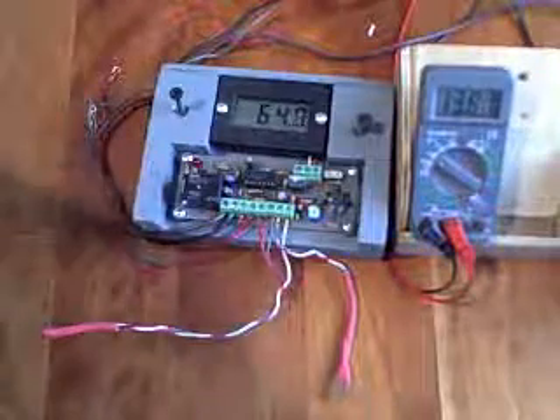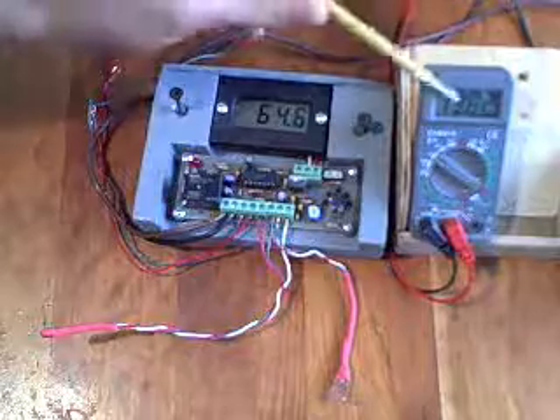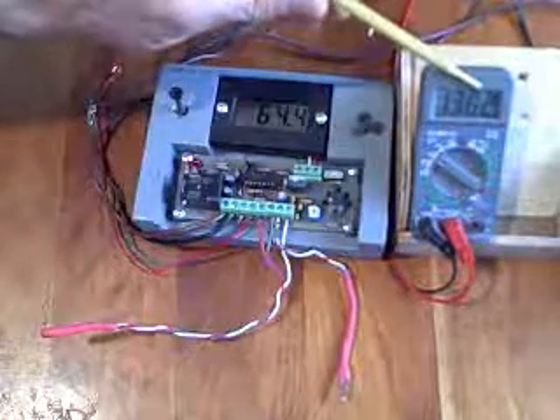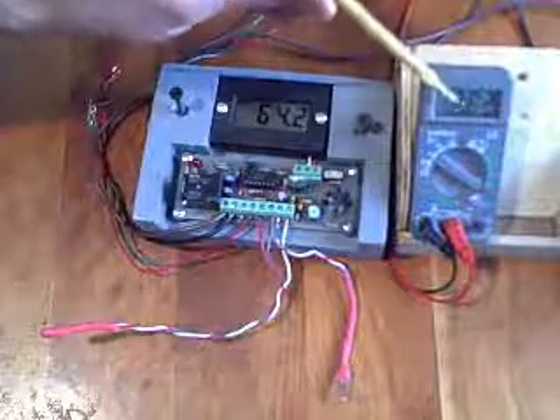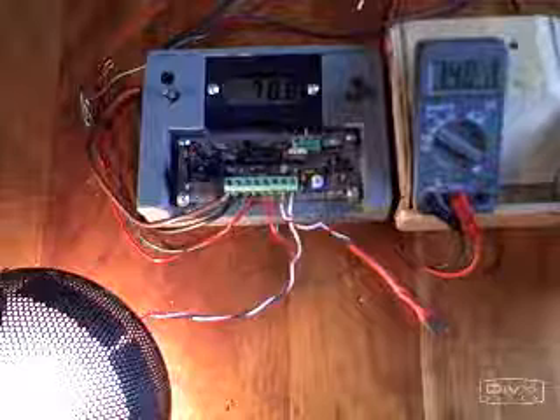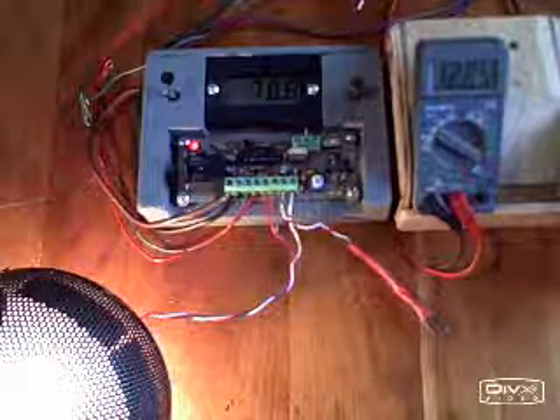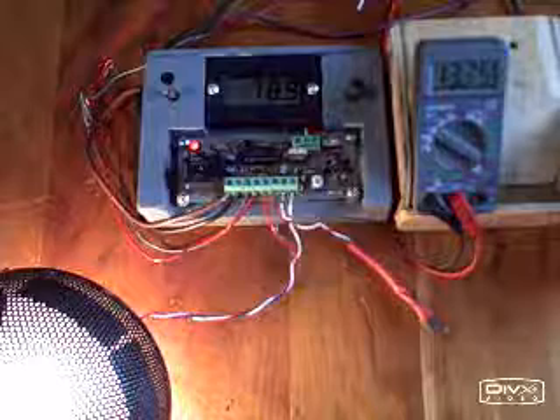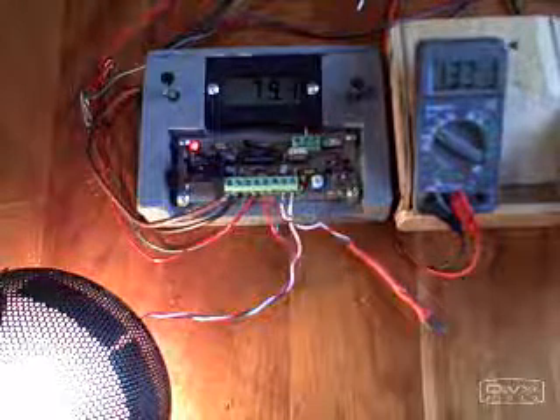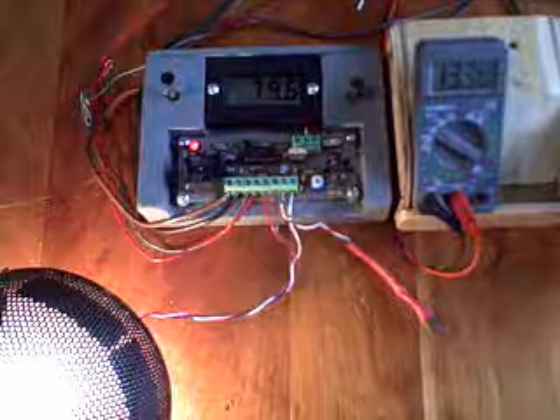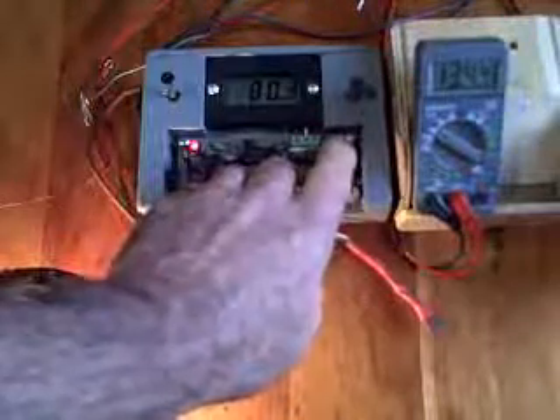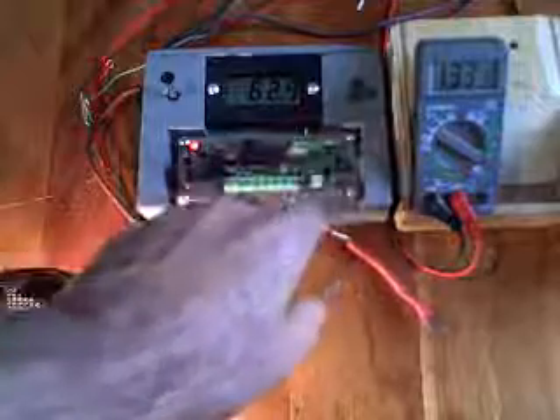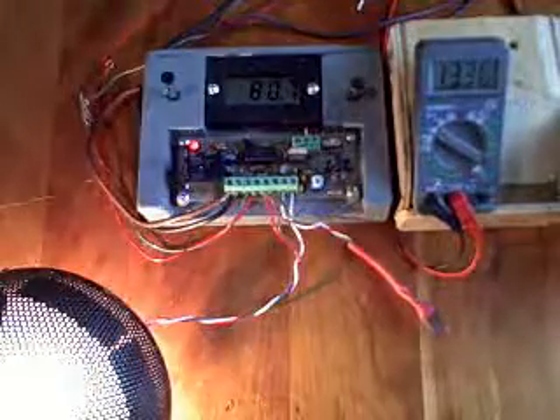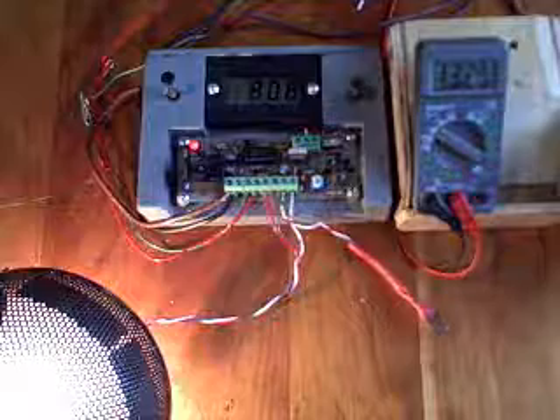Now, the next thing I want to show you has to do with the effect of voltage on the pump. If the voltage gets lower, the pump is going to turn slower. Alright, so at 78 degrees for the collector, the pump comes on. And it'll stay on as long as the temperature difference between the collector and the tank is high enough. Now, right now, we'll take a look at the temperature in the tank. You know, the temperature in the tank is 62, almost 63 degrees. So that's a difference in temperature of about 17 degrees.